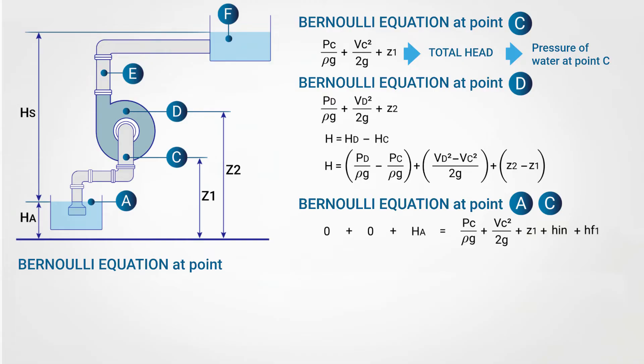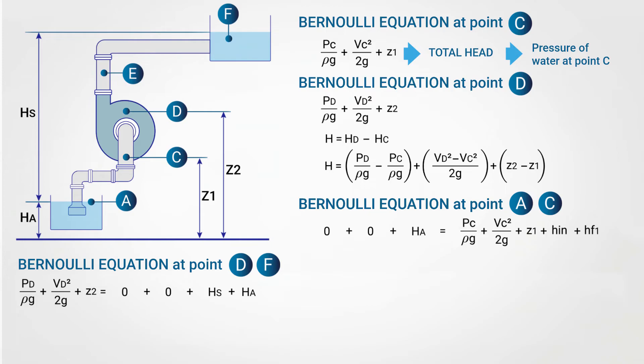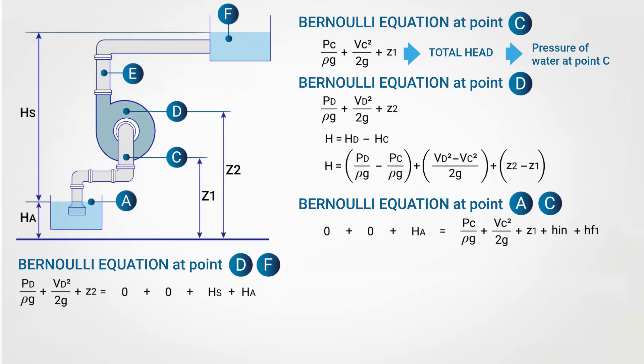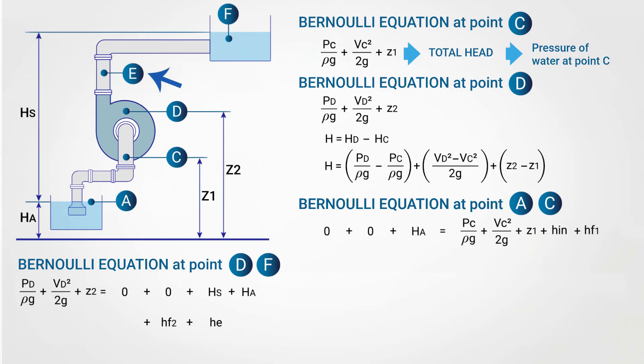Applying the Bernoulli equation at points D and F: the total head at D is PD/ρg plus VD²/2g plus Z2. At point F, the pressure head is zero, velocity is zero, and the height is HS plus HA. Between point D and point F there are losses: HF2, the friction loss in the delivery pipe, and HE, the loss due to water leaving the delivery pipe and entering the upper reservoir.